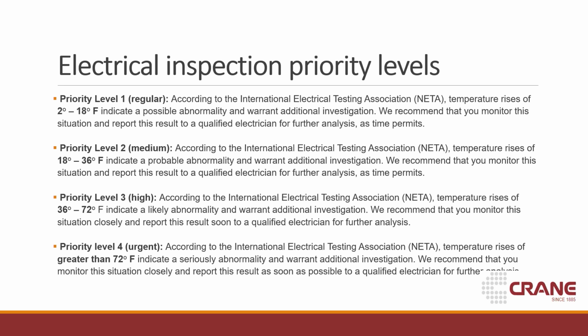I've seen them go all the way up. At the last place I did, I saw priority level 3, a 40 to 50 degree difference from ambient temperature. That's a high difference in temperature for what this place was doing. They were able to get an electrician in there and replace that breaker before it got even higher, where we're talking a higher potential for a fire.